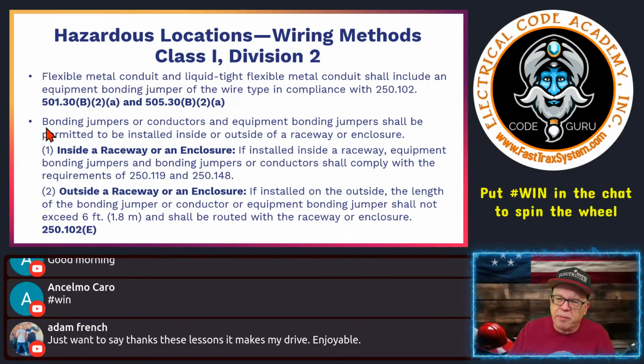It says bonding jumpers or conductors and equipment bonding jumpers shall be permitted to be installed inside or outside of a raceway or enclosure. So you may need a bonding jumper over a meter. You may need a bonding jumper over a piece of equipment. Maybe there's an actual joint that's a dielectric separation and you need to make it continuous. So you may have a jumper. It may be in the raceway or it may be up to certain lengths outside of a raceway in order to do this.